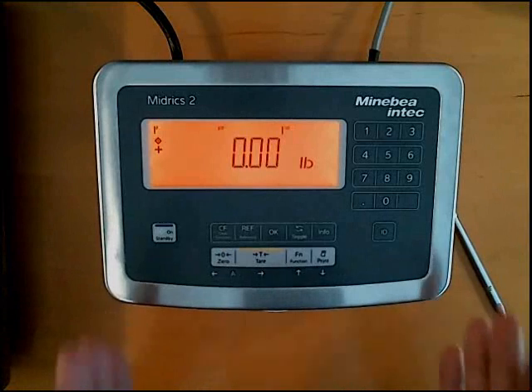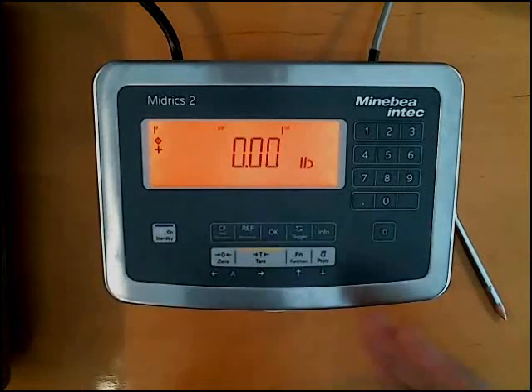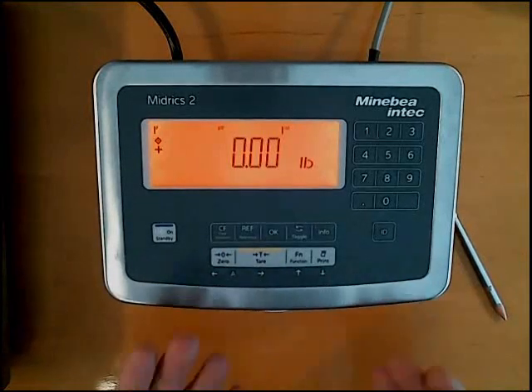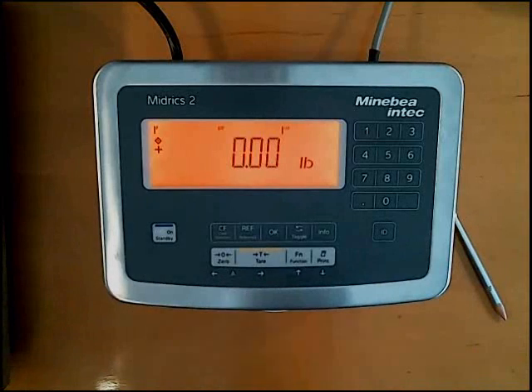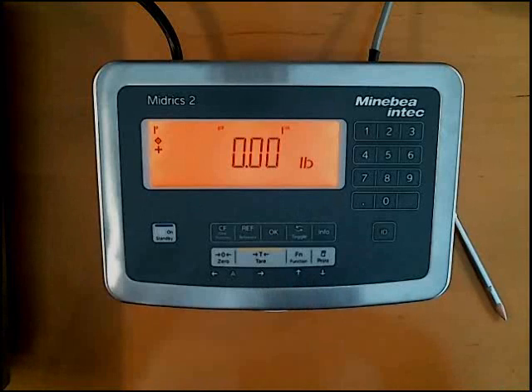But that's not a problem still, because if you just put the scale back into the service mode, perform your calibration again, it will accept the value that you tell it. Okay, so it gives you more control over the calibration. Okay, so there you have it. It's super easy to do. As you can see, from start to finish, it took us less than 10 minutes with me talking all the way through it. Your technicians out in the field probably take them 5 minutes to get it all set up, and your customers up and running.